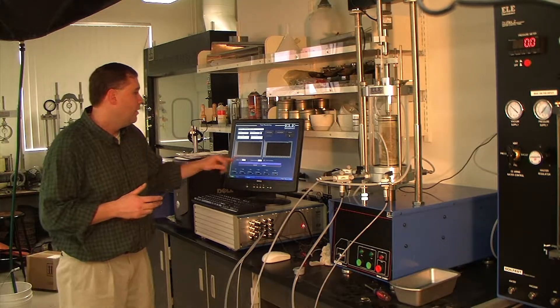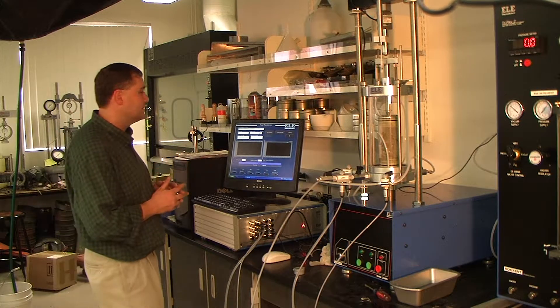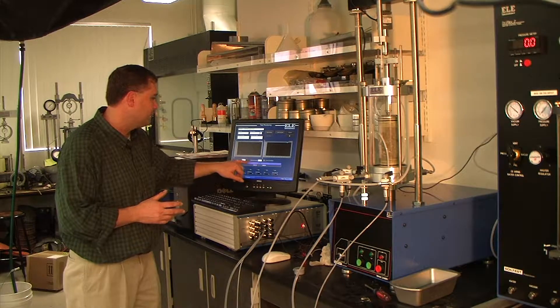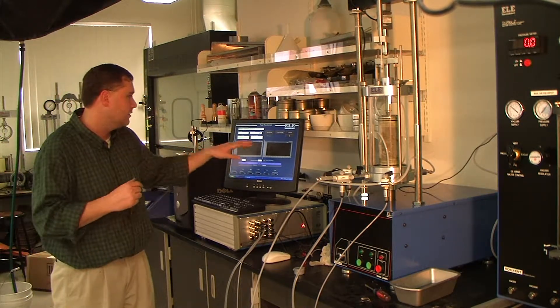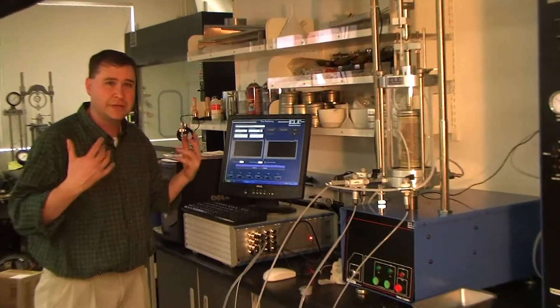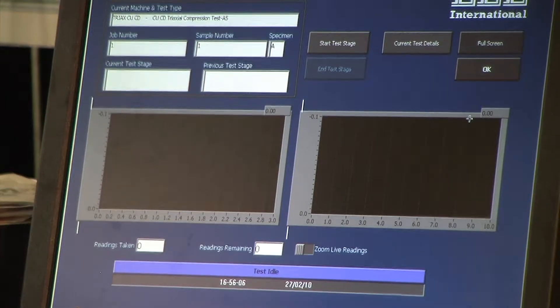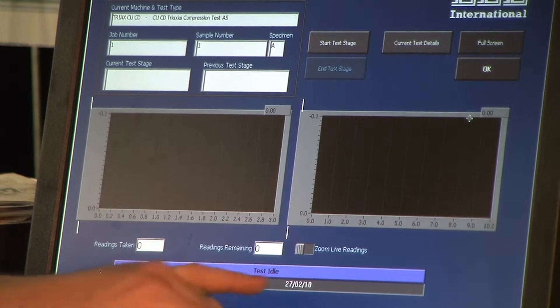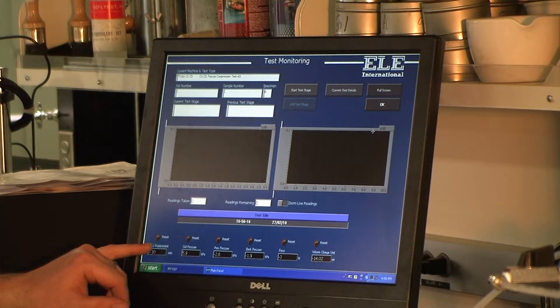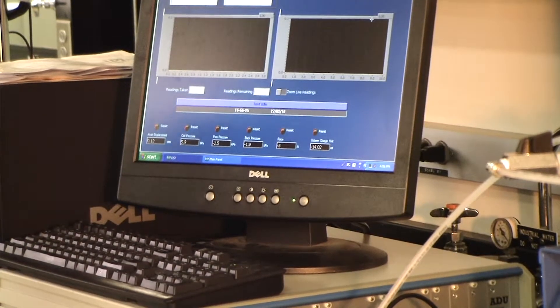What it does is take real time readings. If, for instance, you've been saturating a sample for two days and you want to see what changes have occurred, you can look at readings taken and remaining — say you've taken 31 readings and have 20 left. You can use these as a reference point and also confirm when a new reading has been taken. Beneath that you have a status bar — it says 'test idle' now because we're not doing anything, but it explains what's going on: whether it's taking data or if there's an error. Then you have time and date, and at the very bottom all transducers associated with this machine in a live reading changing every second, though these are not recorded to any file — just for monitoring.